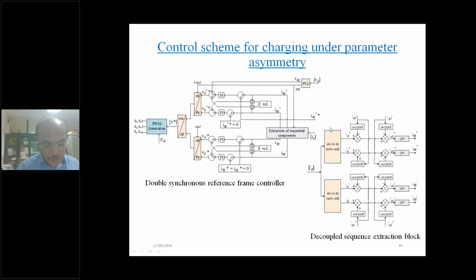We have built a control scheme to maintain balance in the current and remove oscillation on the DC grid, using a decoupled sequence extraction block and double synchronous reference frame controller. This should help maintain current balance as well as do away with double oscillations on the DC side. So we could achieve that part.